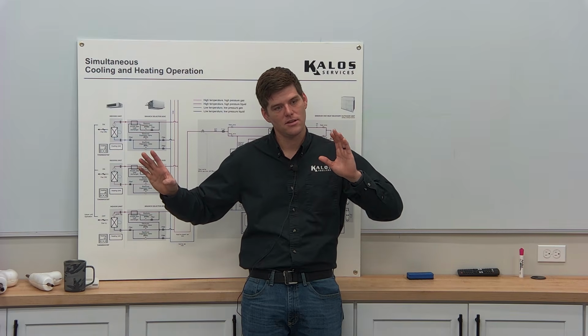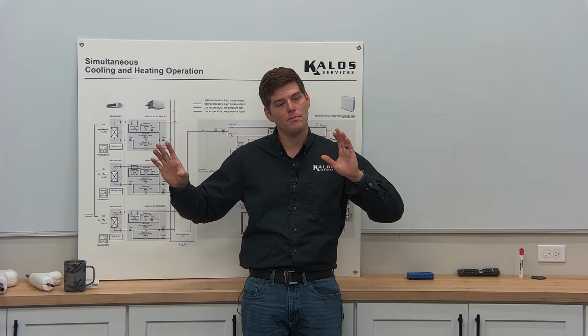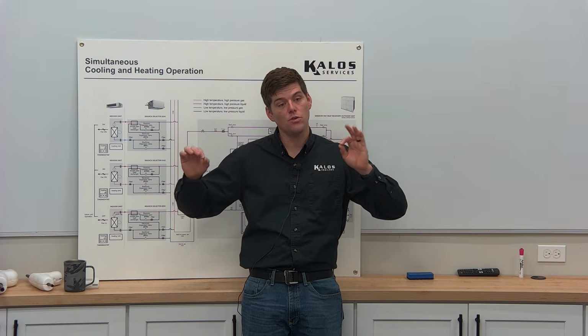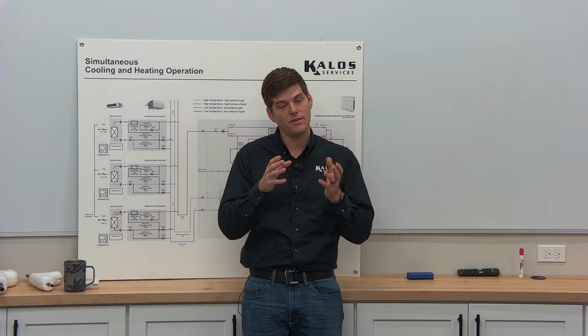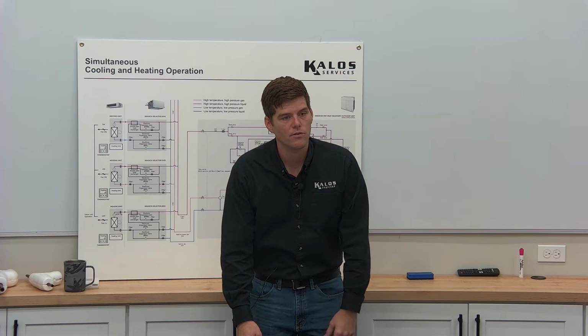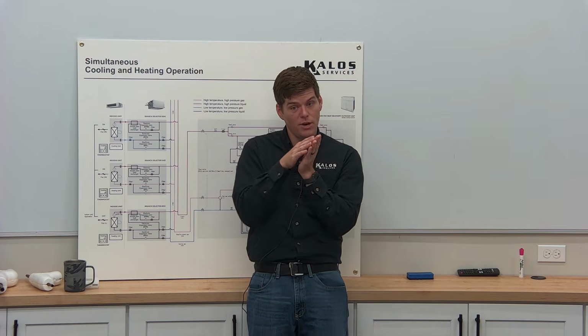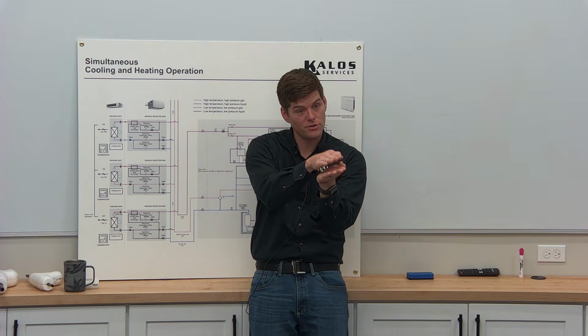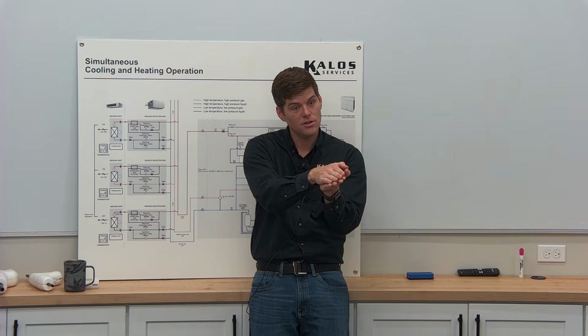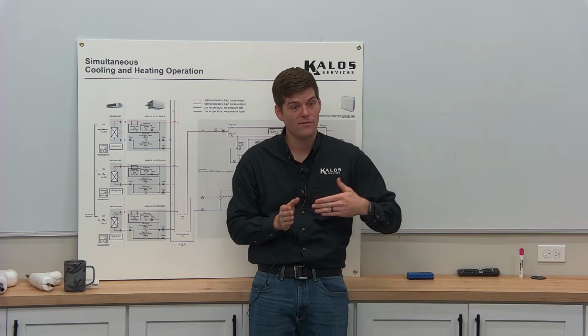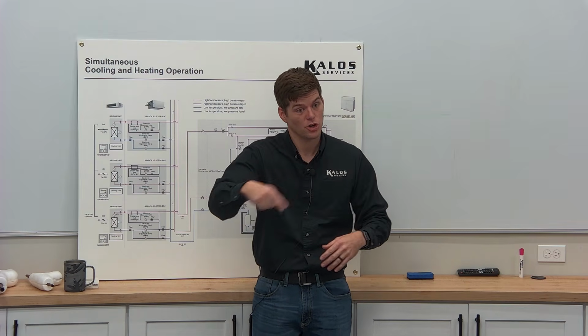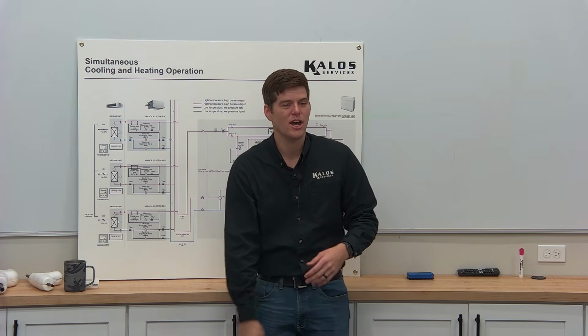Out of gravity or out of rejecting? Mitsubishi owns the technology, and so they won't, I mean, you could tear one apart if you wanted to. But when it comes to the actual box itself, there's a separation that takes place between the actual liquid and hot gas in that line. Which is why they have specific rules as to why you can't have 90s before the boxes. Otherwise, it creates a turbulent flow, mixes it all up, and you kind of get a slurry.